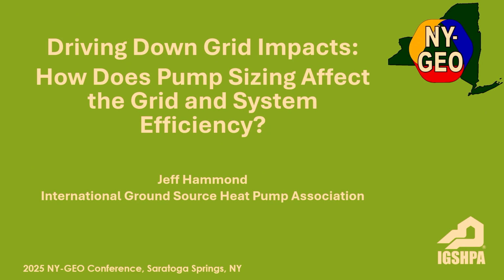That means the cooling load is, even if we're cooling the building with domestic hot water production during the summer, or at least the loop we're cooling. And all that heat ends up in the loop field. Heat is the enemy because the design for the loop field is driven by the cooling load because it's the dominant load. So yes, you're saving $5,000 on a pump and you put a big, very inefficient pump in there, but it's going to cost you 2 or 3 boreholes at $50,000.